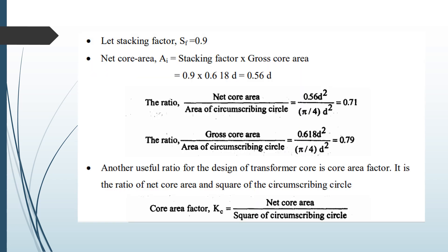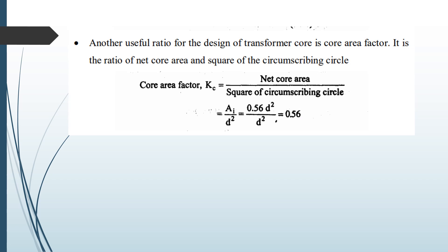The reason we use different types of step cores, such as the two-step core, is to maximize the area utilized within the circumscribing circle and to reduce the space wasted between the coils and core. The core area factor for a two-step core can be calculated simply by dividing the net core area by the square of the diameter of the circumscribing circle.